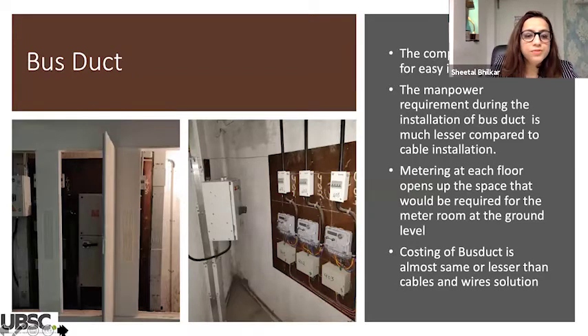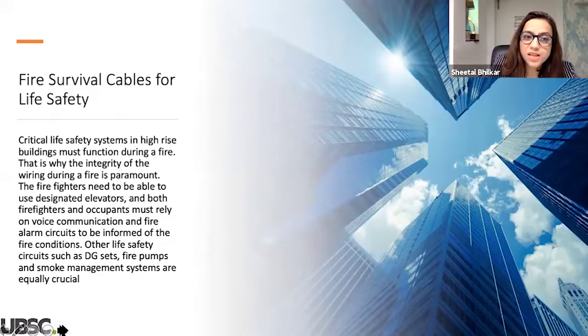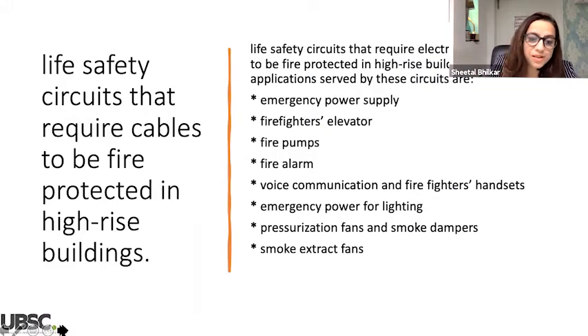bus duct installation. Then again, fire survival cables should be used for life safety, which is mandatory as per fire NOC, but some people don't follow this. But as consultants, we should ensure that all builders are using these fire safety circuits with fire protected fire survival cable. So emergency power supply, firefighting elevator, fire pumps, fire alarm circuits, voice communication, firefighters handsets, emergency power for lighting, pressurization fans, smoke dampers, smoke extract fans. All these circuits should be fed with fire survival cables.